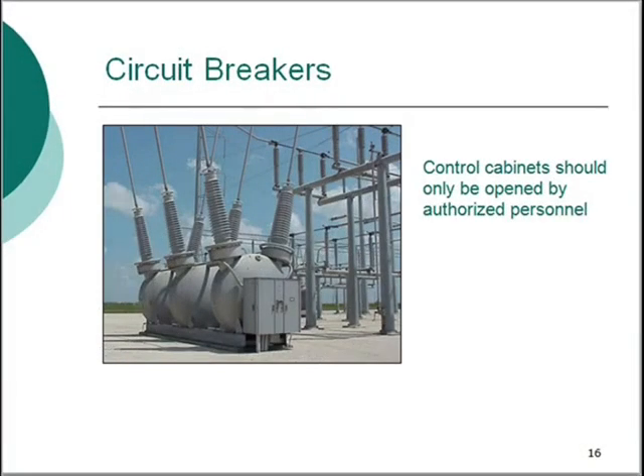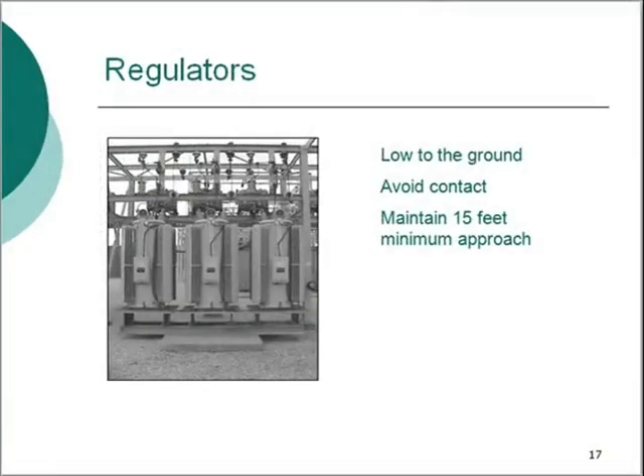Circuit breakers are used to isolate equipment for maintenance. The breaker tanks are pressurized. Control cabinets contain both electrical and mechanical hazards and should only be opened by authorized personnel who have been trained and qualified in company operations and maintenance procedures. Stay away from the bushings and lines on top of breakers. Voltage regulators are used on distribution circuits. The wires attached to the top of the regulators are sometimes low to the ground and within reach. Specific hazards such as this should be identified in job briefings and safety discussions. Maintain 15 feet minimum approach distance unless you have received additional safety training specific to this equipment.